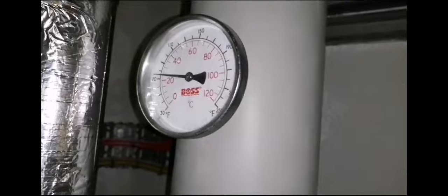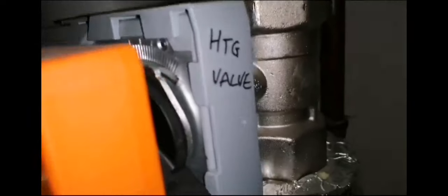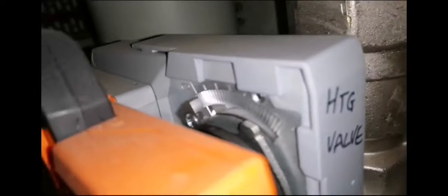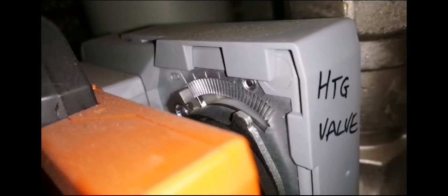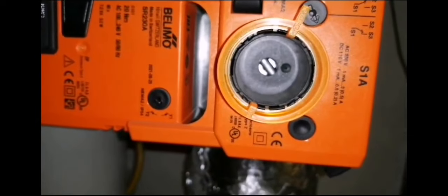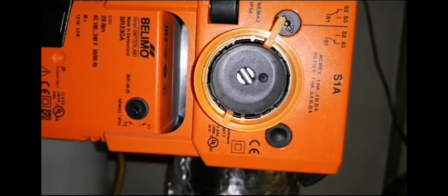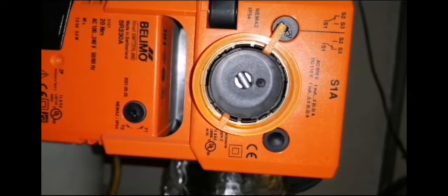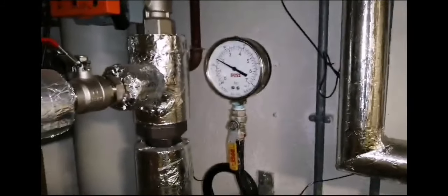You can see the temperature here dropping as the valve opens because it's sort of blending with the water that's inside the system, which I believe is at about 20 Celsius. This has been off since like the new year, so it's been probably a good 10 days or so that it's been off, so the building's freezing. You can see the valve opening. And then it will probably take a while for the heating to go up in temperature.